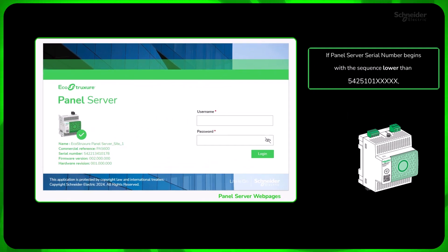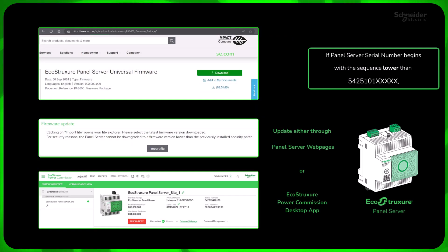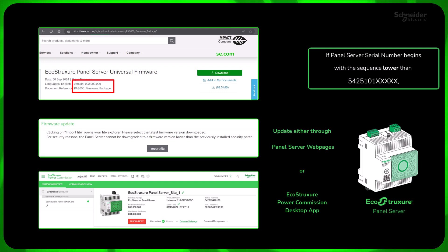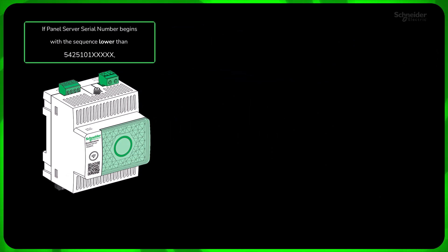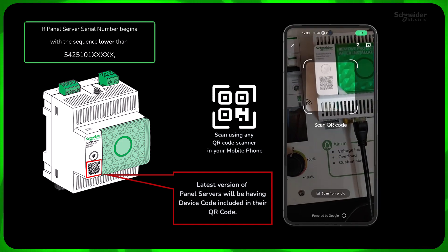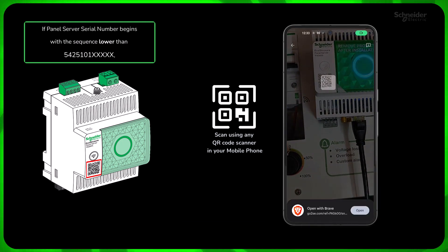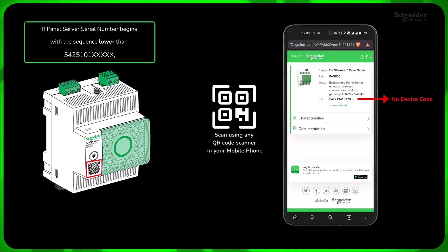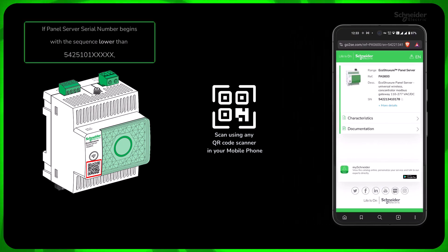If your panel server serial number begins with a sequence lower than 5425101, please check and update the firmware to version 2.0 or above before proceeding. Also, please scan the QR code on the panel server and check if the device code is available. If the device code is not available, you need to find the code from the panel server webpages.